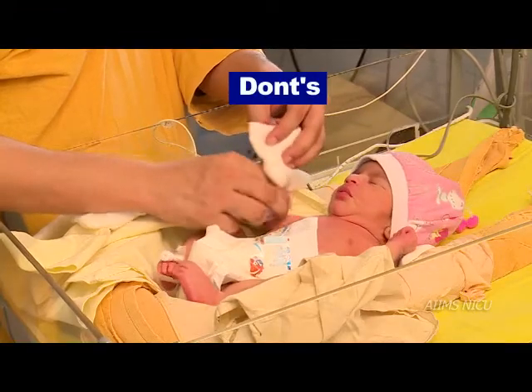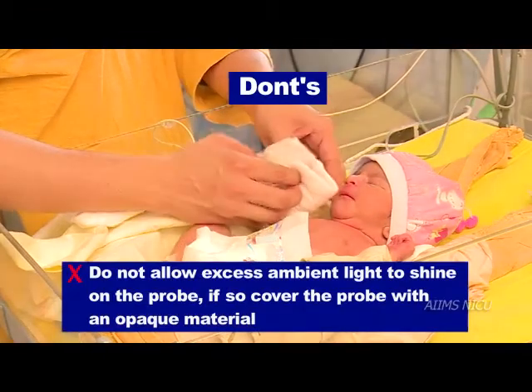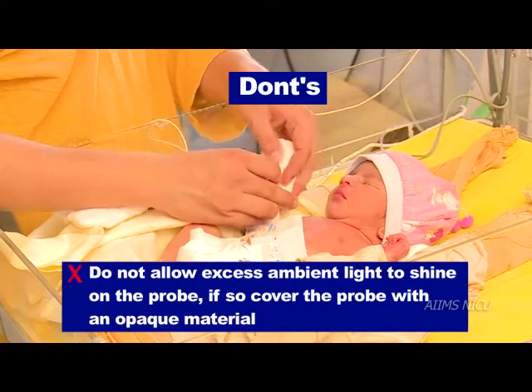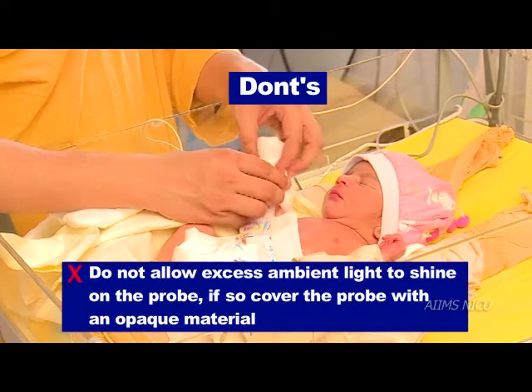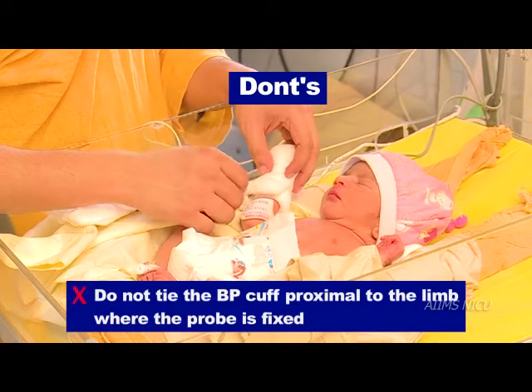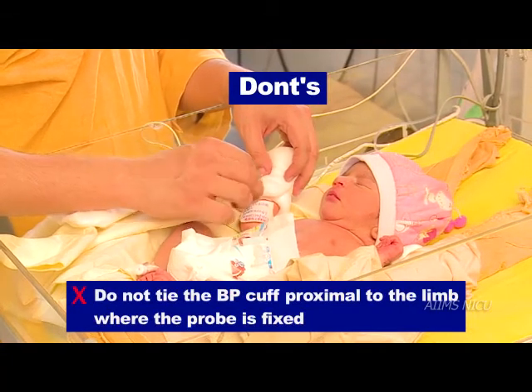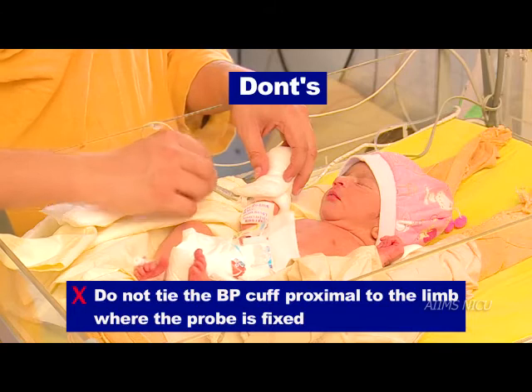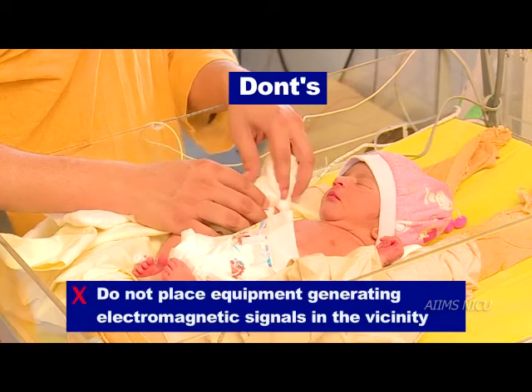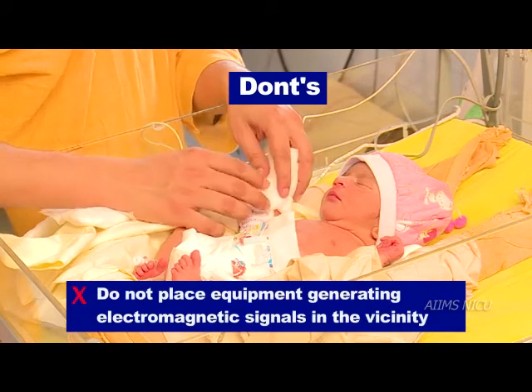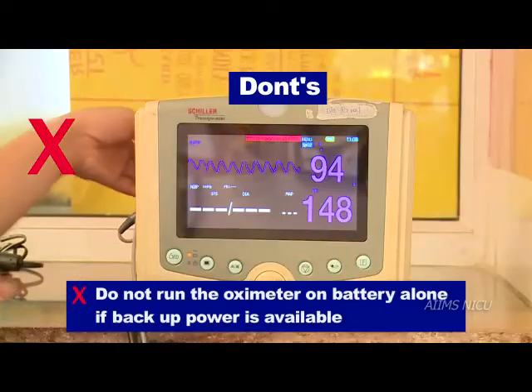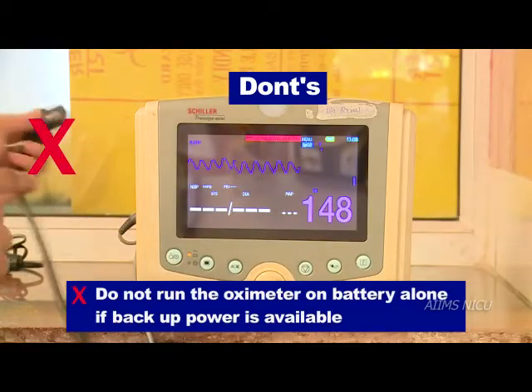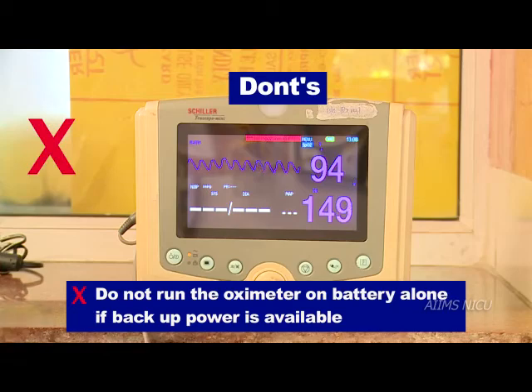Some don'ts. Do not allow excess ambient light to shine on the probe. If so, cover the probe with an opaque material. Do not tie the BP cuff proximal to the limb where the probe is fixed. Do not place equipment generating an electromagnetic signal in the vicinity. Do not run the oximeter on battery alone if backup power is available.